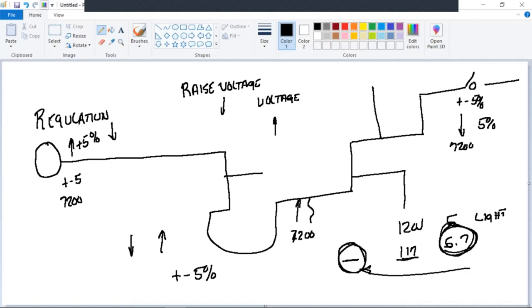Think of the concept. And what they'll do on systems here is, at the voltage regulator, they'll put a communications component, and along the line, they'll put what they call smart meters. All through these areas, right through here, all the way to the end. Not on every house, but through, you know, major distances, or design distances that are in the system. And this meter will send information back to the breaker. I'm at 117. Okay, everything's copacetic. And I'm at 122. Everything's kind of good right there.